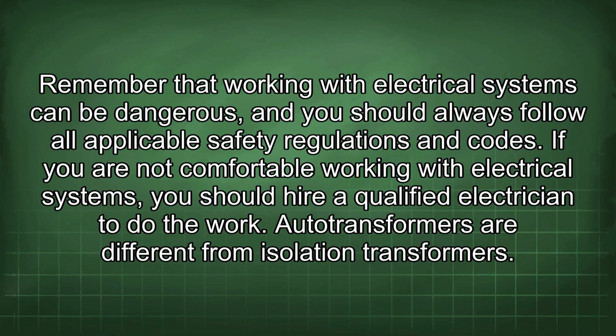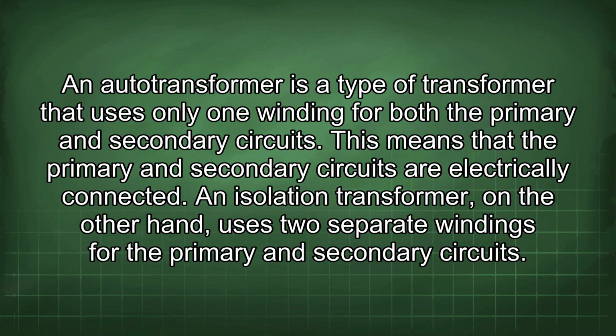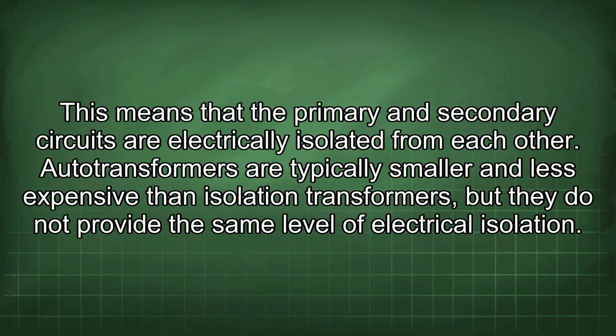Autotransformers are different from isolation transformers. An autotransformer is a type of transformer that uses only one winding for both the primary and secondary circuits. This means that the primary and secondary circuits are electrically connected. An isolation transformer, on the other hand, uses two separate windings for the primary and secondary circuits. This means that the primary and secondary circuits are electrically isolated from each other.